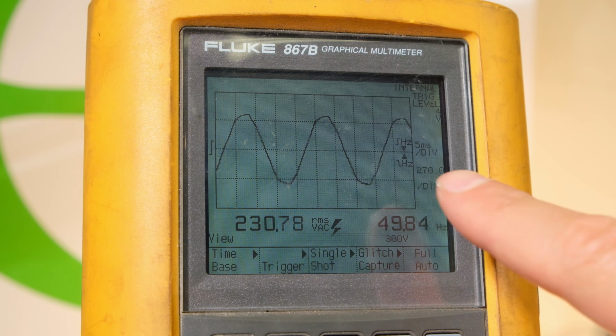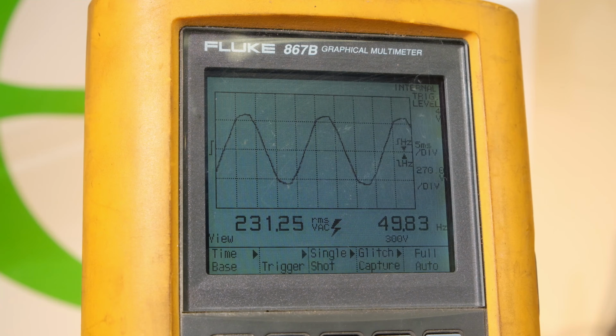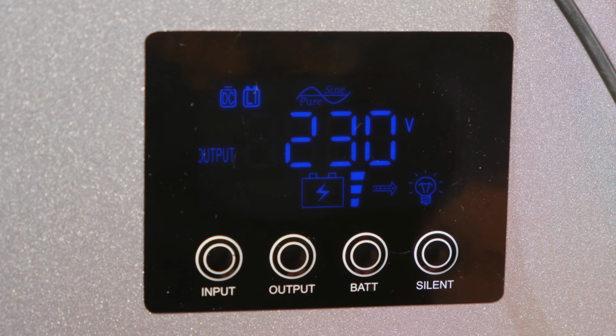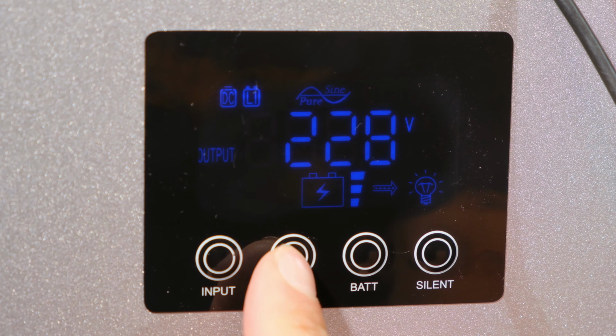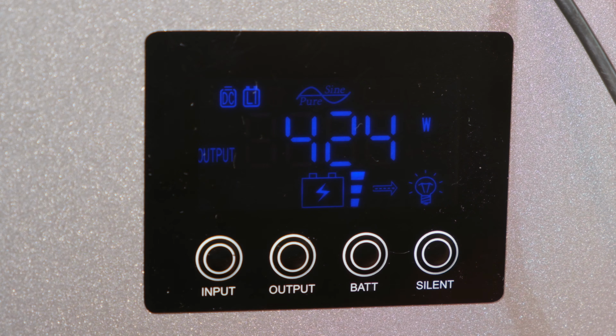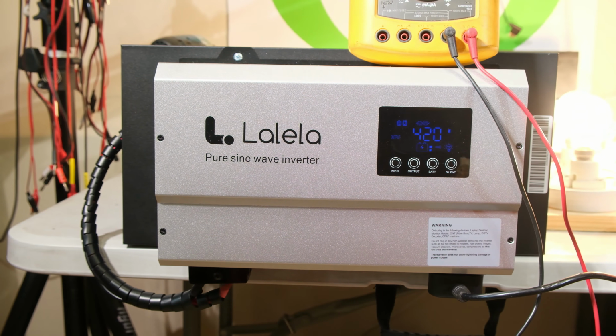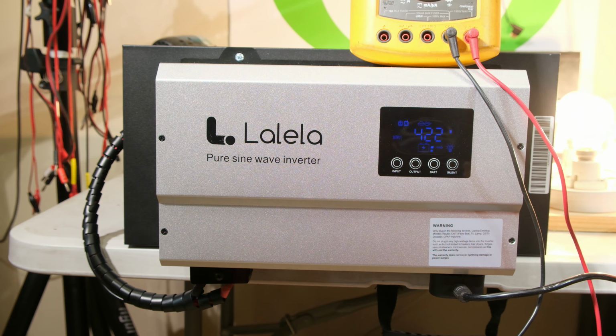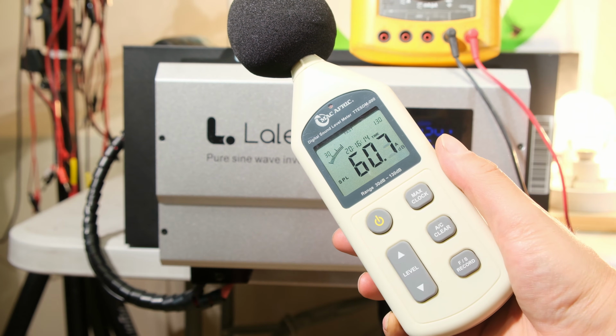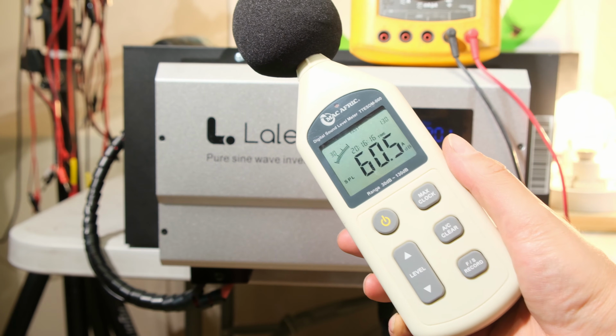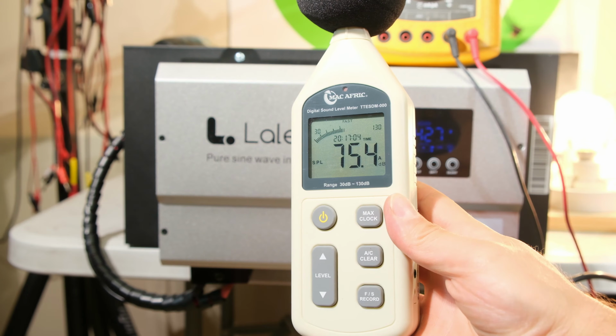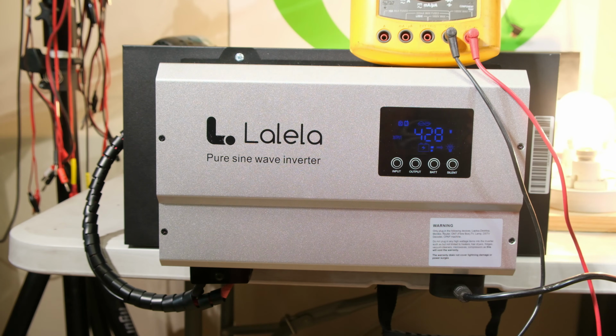What is nice is that the output is a clean sine wave and the duty cycle is stable and the voltage is good. I've disconnected the mains and just quickly having a look at the output, and at the moment it's feeding 424 watts. And the fan is on because, as I said earlier, if you load it above 38%, you are going to hear that fan noise. And if you're wondering how noisy that fan is, I'll quickly measure the sound pressure level. The fan noise at about half a meter from the unit is about 60 decibels. It is fairly noticeable. And the alarm beep is at about 75 decibels.